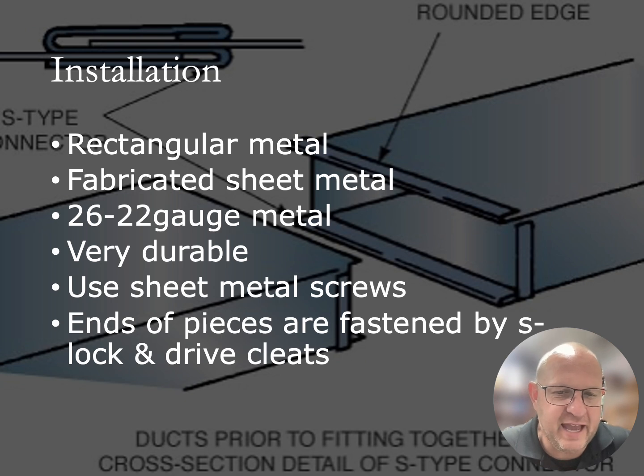For the most part, the gauge of the ductwork is running somewhere between 26 and 22 gauge metal. The thicker the gauge of the metal, the more rigidity it has and its ability to withstand popping noises.